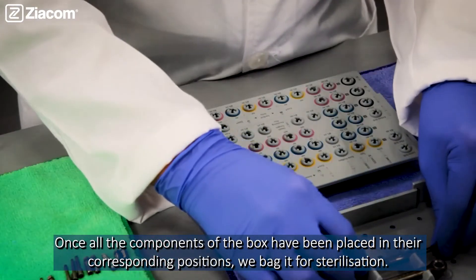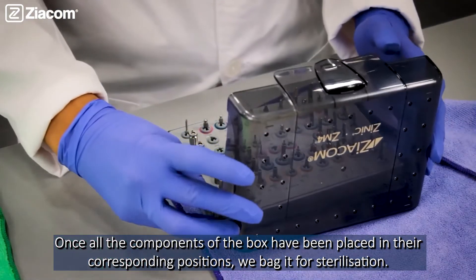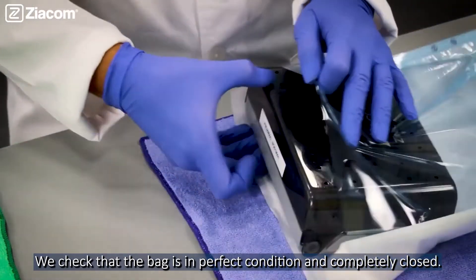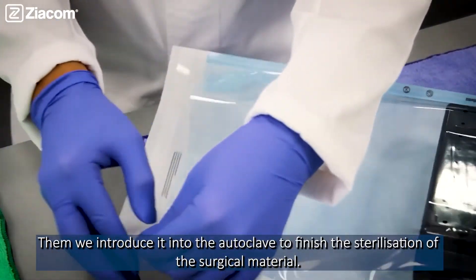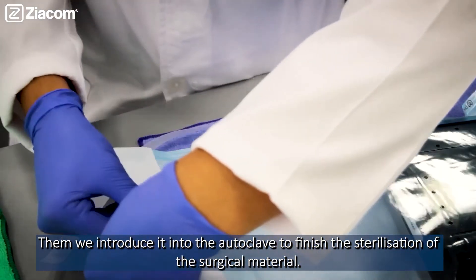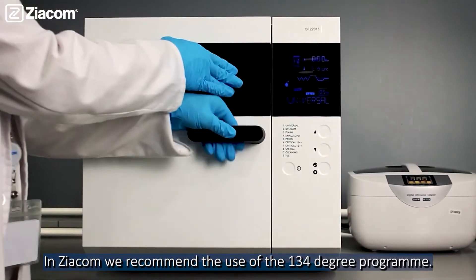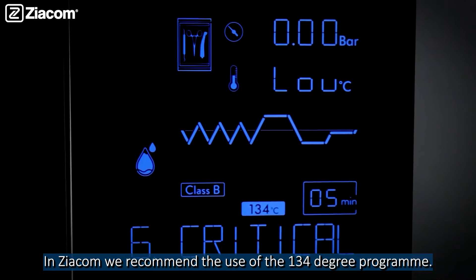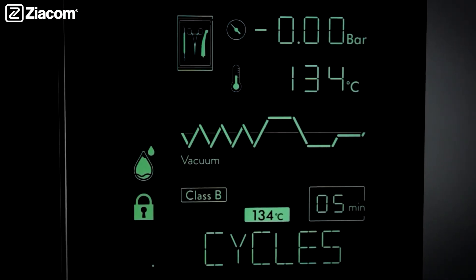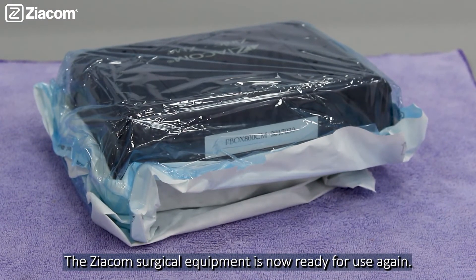Once all the components of the box have been placed in their corresponding positions, we pack it for sterilization. We check that the box is in perfect condition and completely closed. Then we introduce it into the autoclave to finish the sterilization of the surgical material. Ziacom recommends the use of the 134-degree program. The Ziacom surgical equipment is now ready for use again.